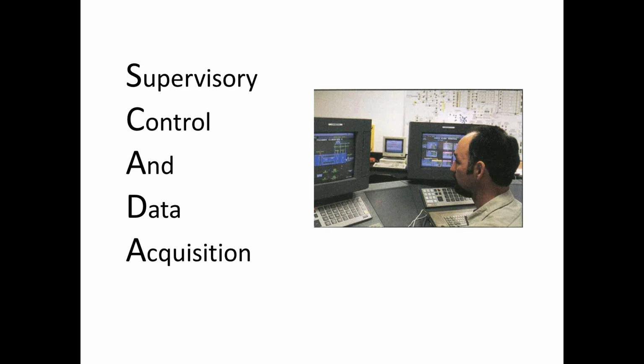And the PLC is getting all this input and output, and it can record a lot of that data. If you wanted to get a past trend of dissolved oxygen levels in your aeration basin, for example, the DO sensors send that DO signal to the PLC, which relays that information to the SCADA system. The SCADA system records and maintains that data, so you can go back and look over a period of time to see what the DO levels are, and you can get a trend of the DO levels. So acquiring and retaining that data is instrumental to being able to troubleshoot the process and monitor the process to see that it's working well.